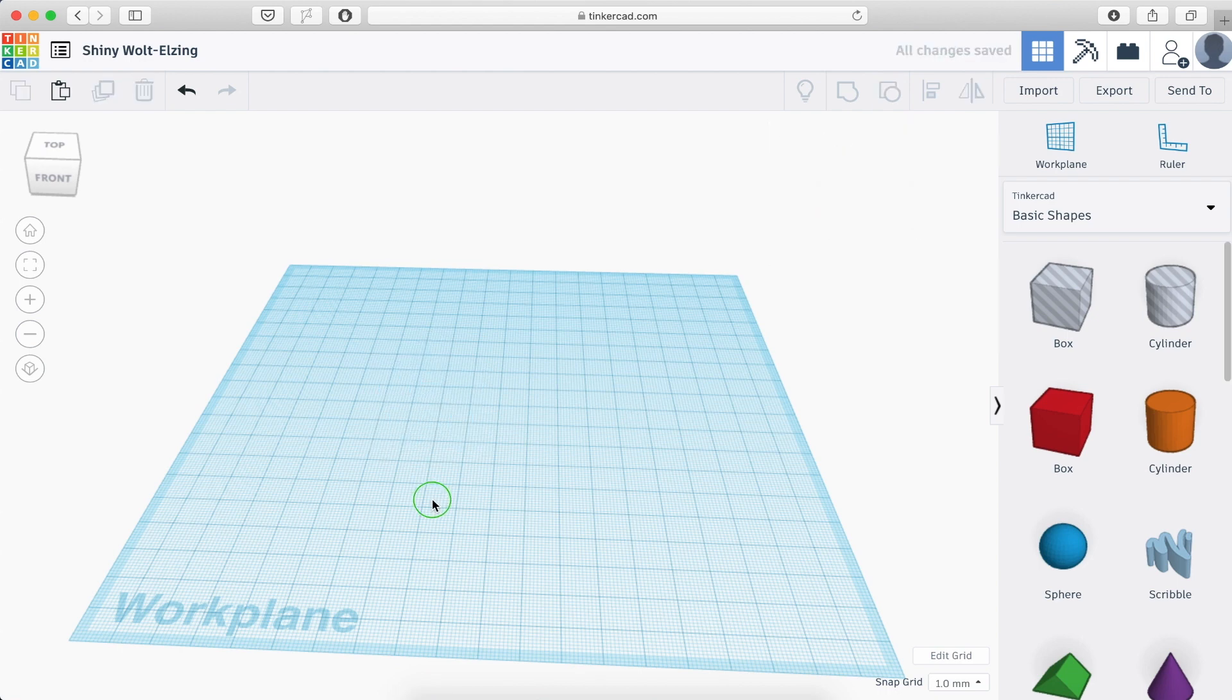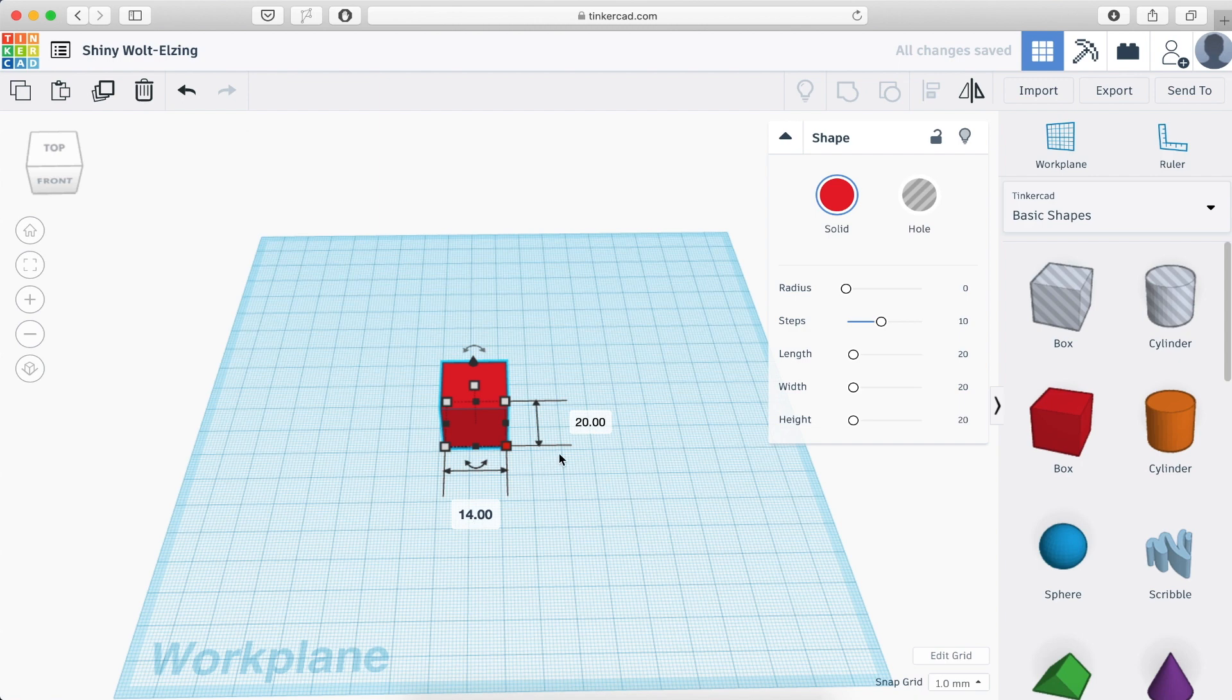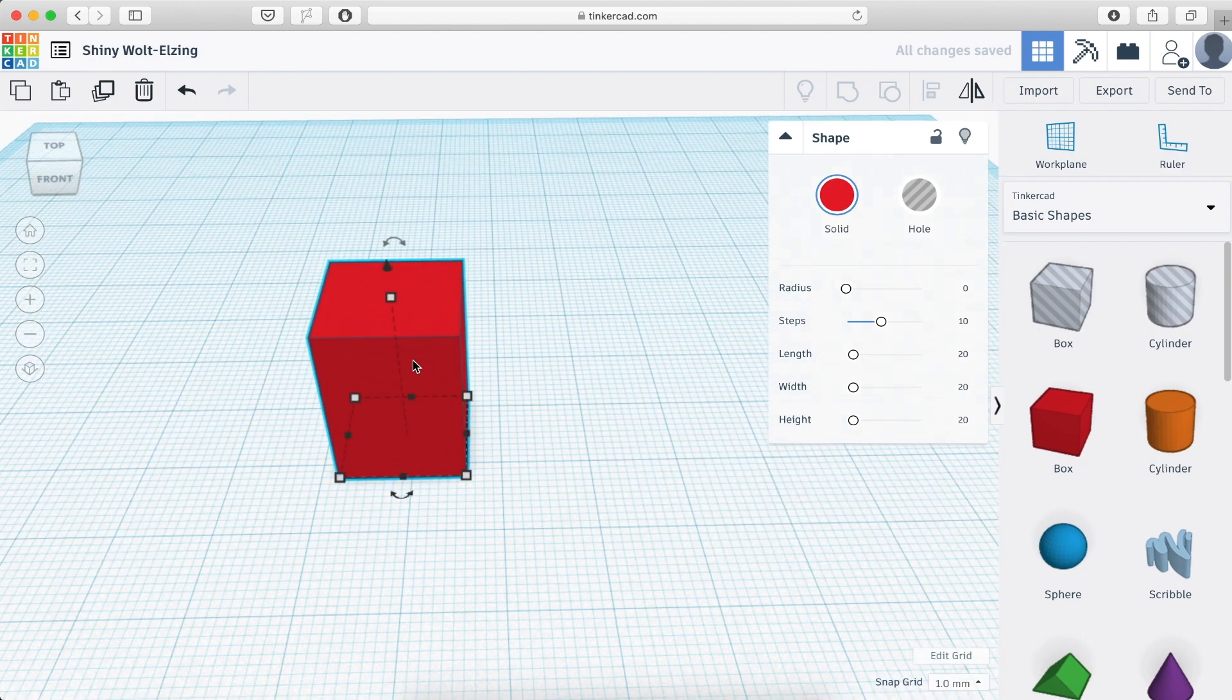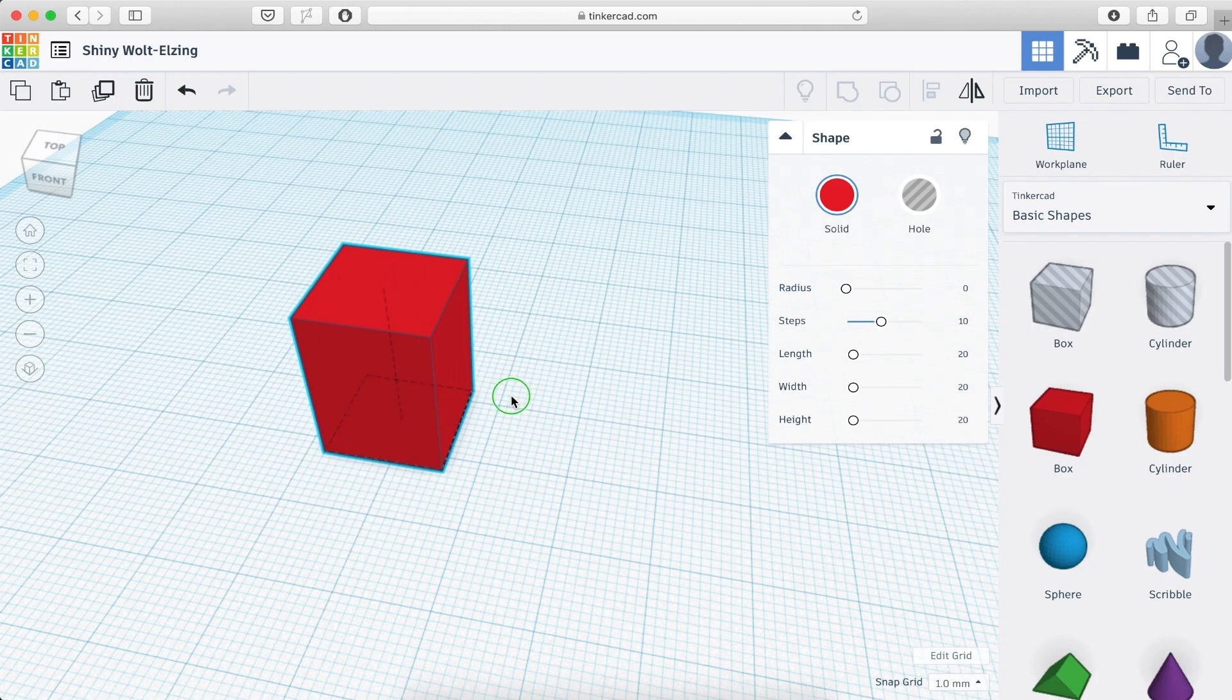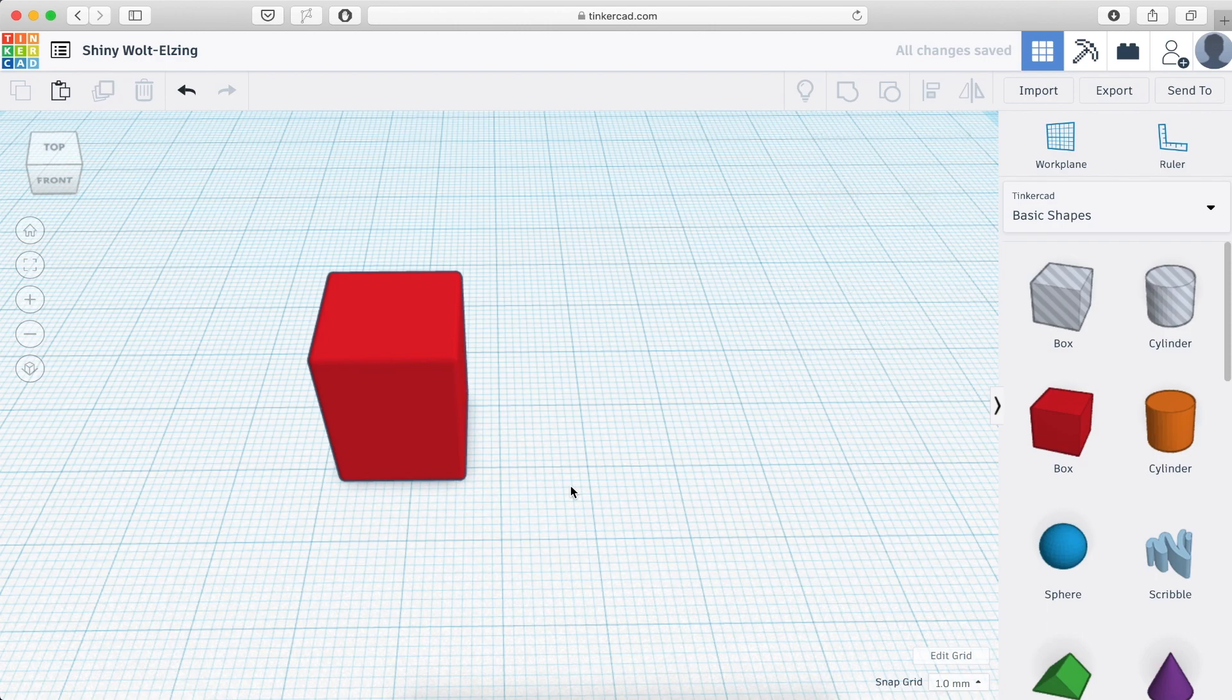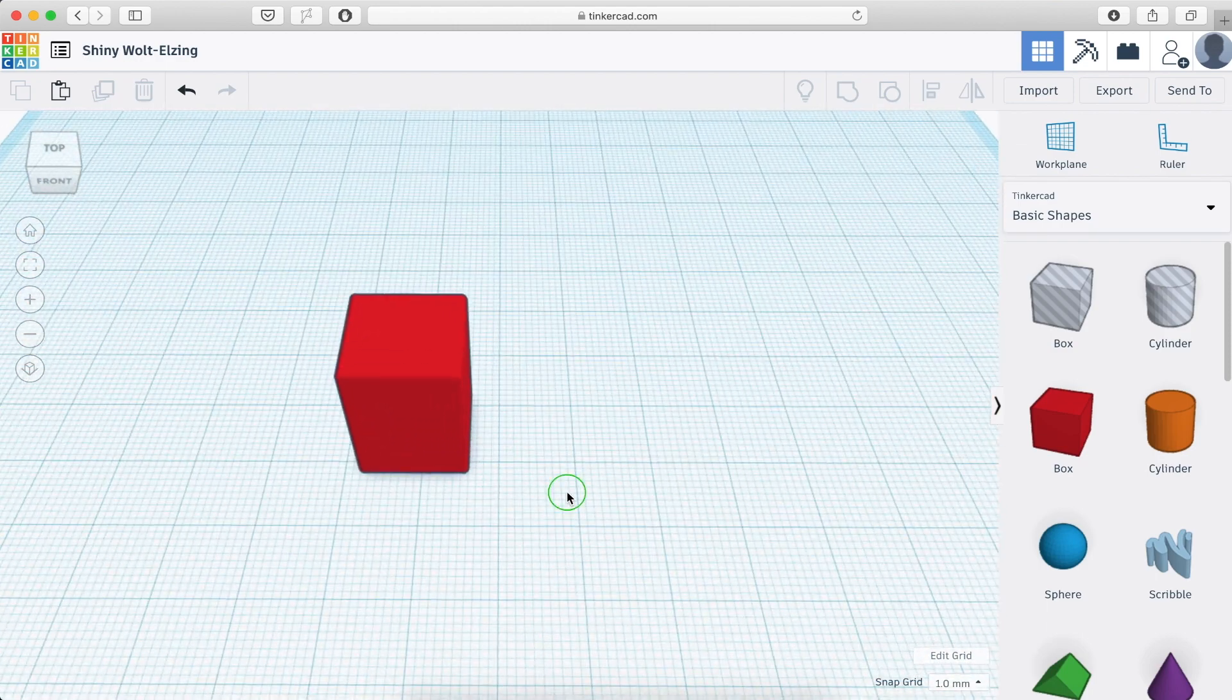So how to design a cuvette holder? First of all, I will start designing the holes itself for the cuvette. This one should be 14 millimeters and 14 millimeters. This is the size of the hole for the cuvette. And another thing that I want to do, I don't want to have sharp corners. I want to have something more like this, for example 0.8, so that the corners are not that sharp.